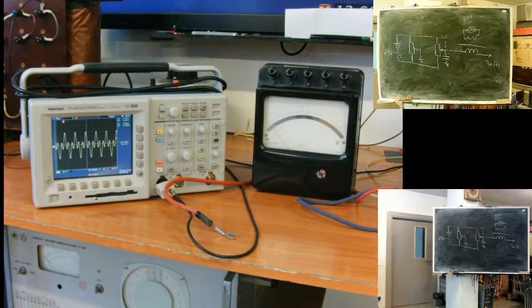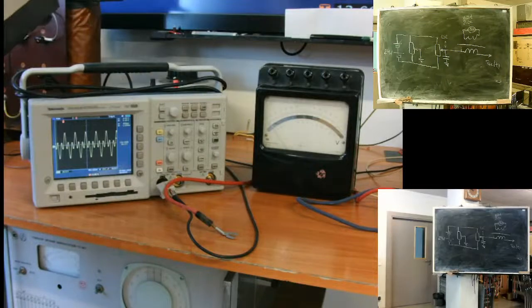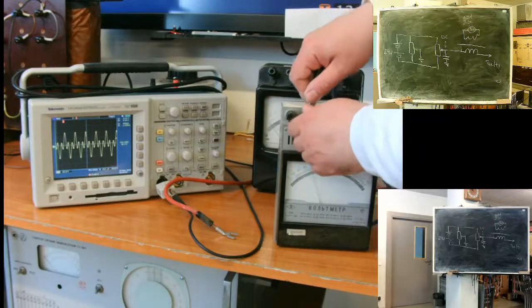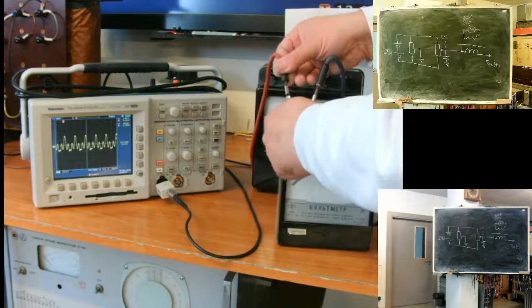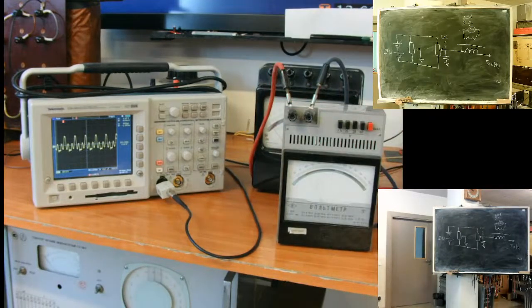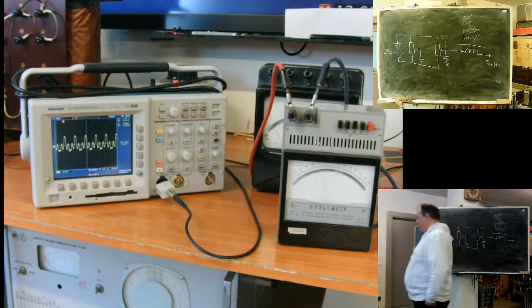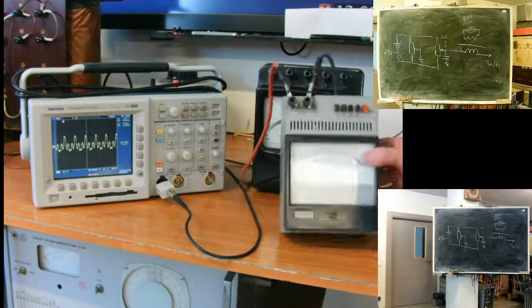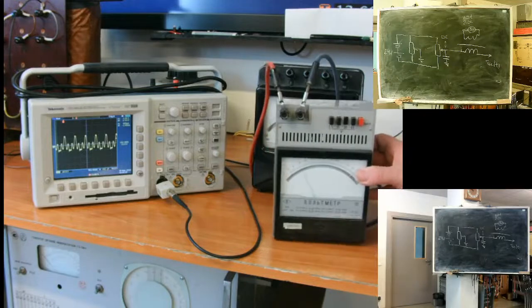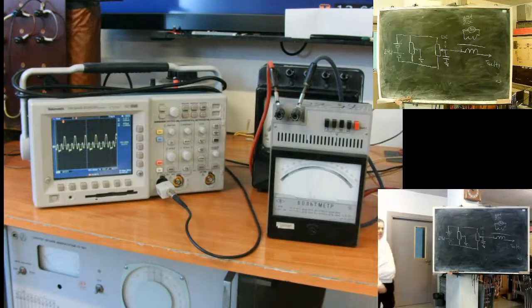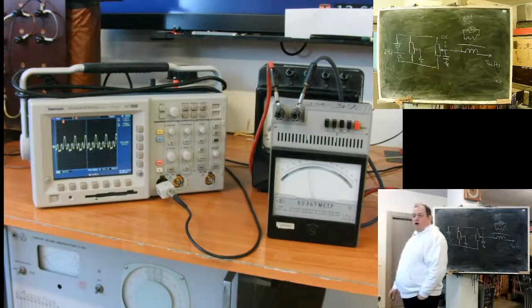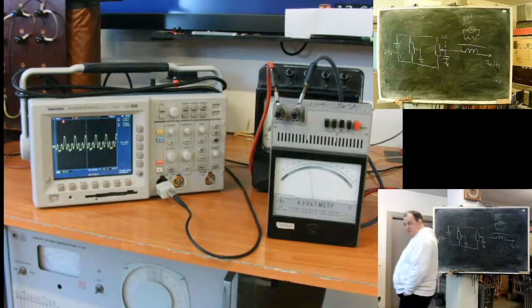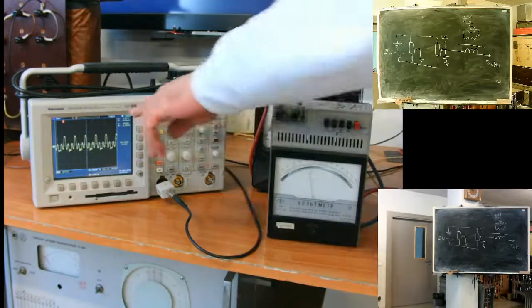For example, I have this moving iron voltmeter. Look what will happen when I attach it to the meter - can you see? It's loading the network so hard, putting such a large burden on the network. At 30 volts it has only 1200 ohm input resistance. Moving iron instruments are known for high consumption from the network - they show effective value but put a high load burden on the network.